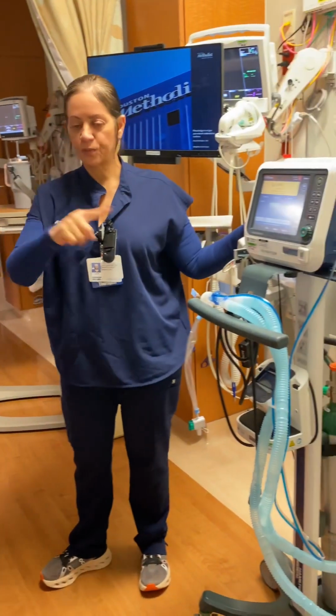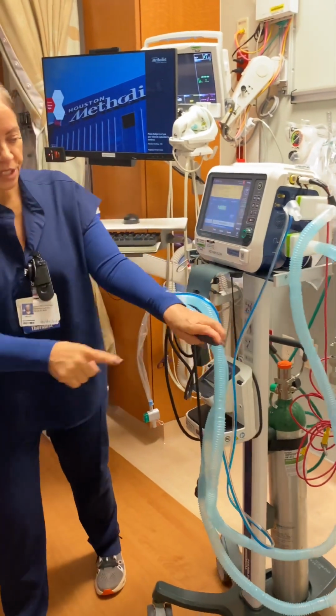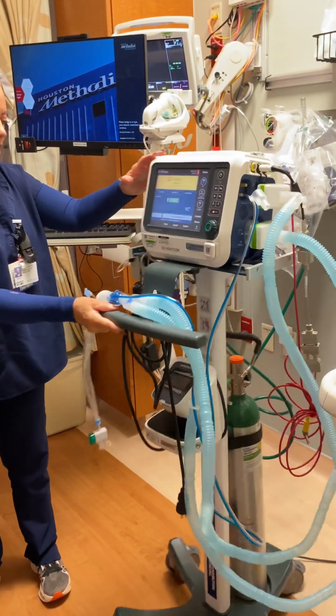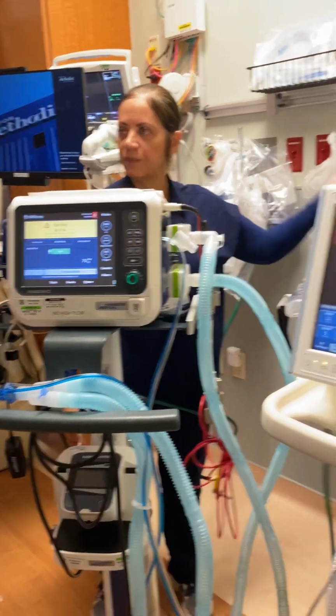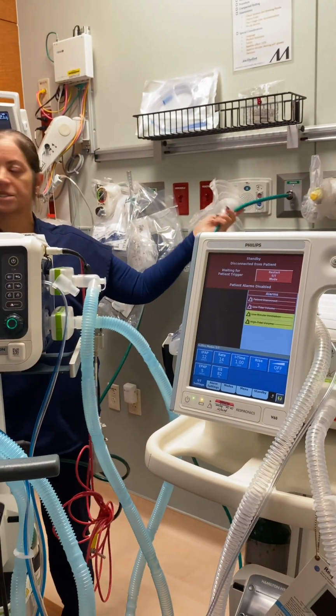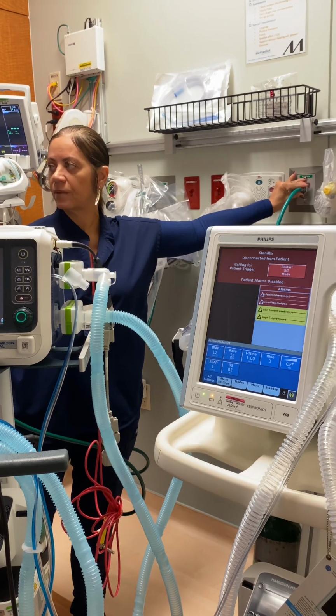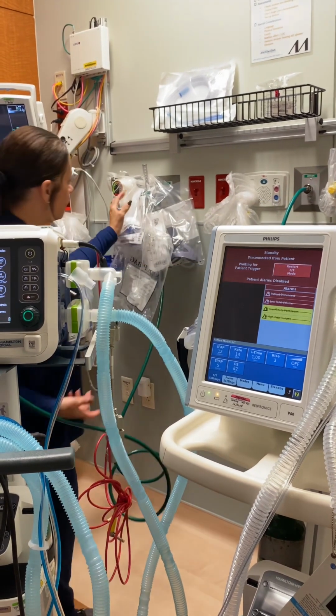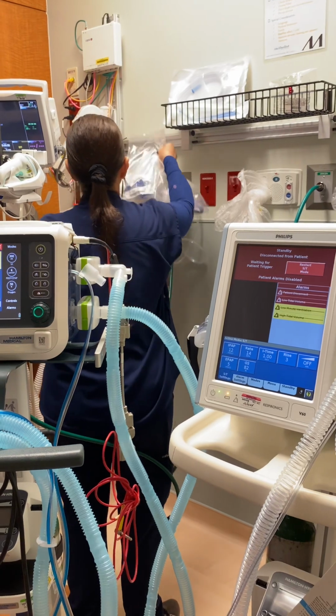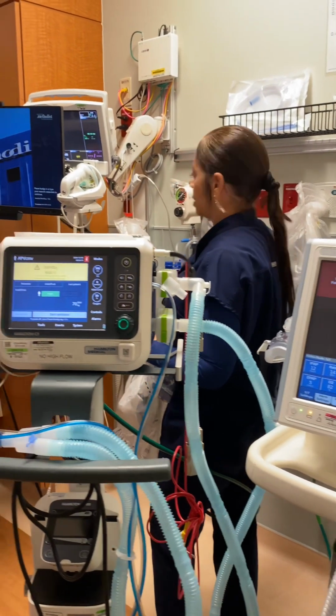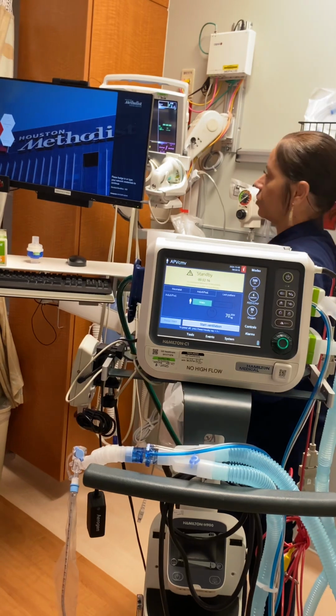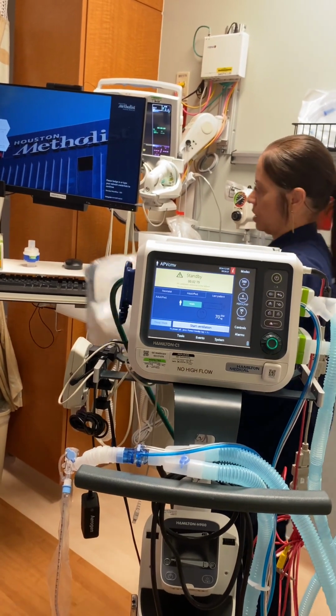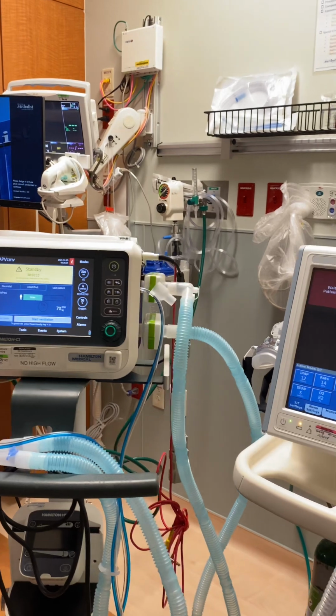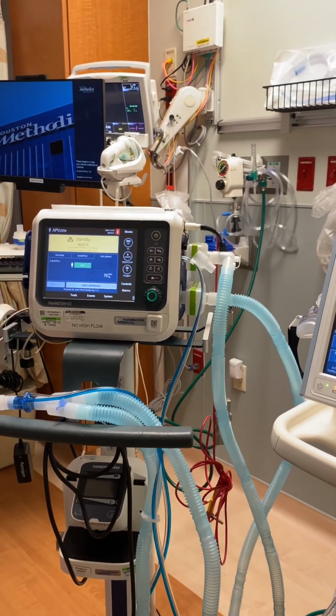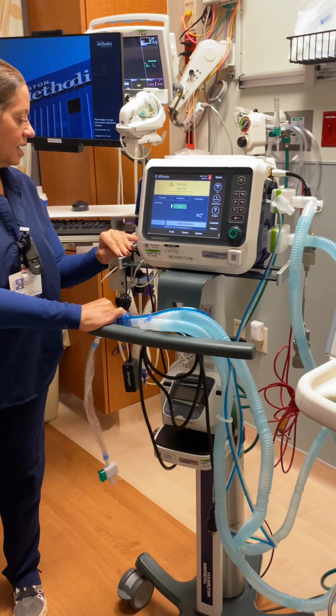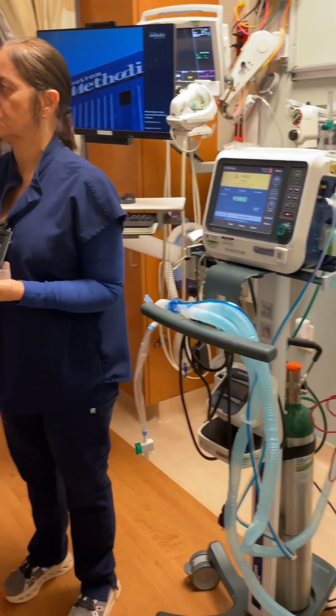Now, we can transport on both of these devices. There's tanks on the back, okay? Now, just like you hook it to the 50 PSI, and when I say 50 PSI, there's 50 PSI, that's a lot of pressure coming out this wall. For the flow meter, you have to hook it to the back of the flow meter, right here. Don't ever hook it to the front. That's a flow, that's not a pressure. It needs to hook to the back. If it's not hooked up to the 50 PSI on the flow meter, this machine will not work. I can tell you. It'll alarm nonstop too. You have to hook it up to a red plug to make sure it says charged up.